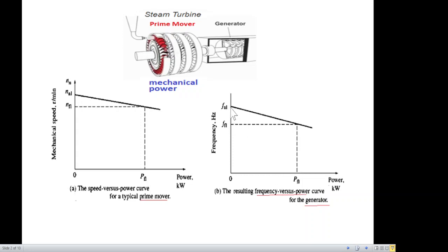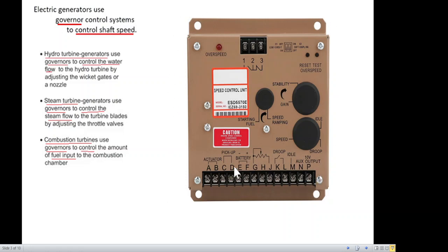As the load increases, the frequency will also decrease from no-load to a full-load value. We must keep in mind that a governor is attached with every generator, and it has various parameters to control — mainly the speed or frequency, which is called the set point of the generator. In a hydro turbine, the governor controls the flow of water; in a steam turbine, it controls the steam flow; and in a combustion engine, it controls the fuel flow to decrease or increase the shaft speed and consequently the generator frequency.